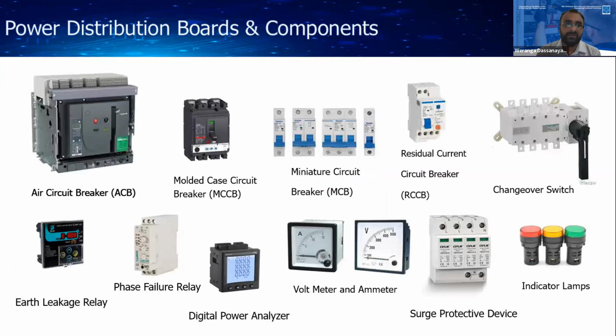These are some pictorial views of the components which I have described previously. First one is the air circuit breaker, which can handle high current. That means about 1000 amperes, we have to use air circuit breakers. Sometimes these air circuit breakers can handle up to 6000 amperes. The molded case circuit breakers can be used up to 1500 amperes, from 100 ampere to 1500. MCBs you can use only up to 50 ampere. After 50 ampere, you must use molded case circuit breakers.